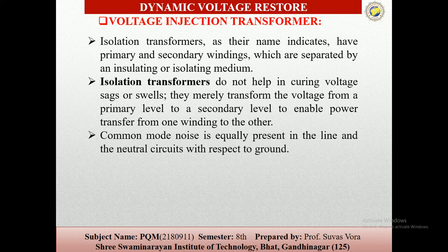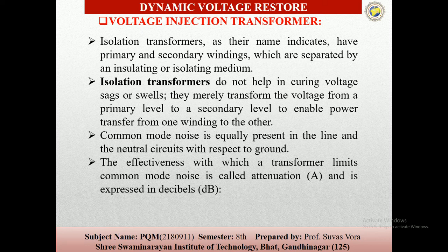The common mode noise is equally present in the line and the neutral circuit with respect to the ground. The effectiveness with which a transformer limits this common mode noise is called the attenuation and is expressed in decibels. So our equation is A equals 20 log V1 by V2.